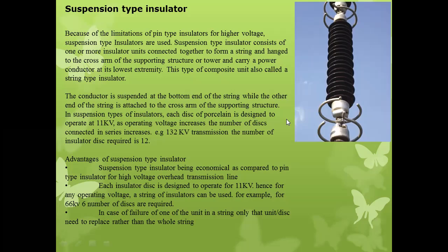In case of failure of one unit in a string, only that unit or disc needs to be replaced rather than the whole string. In the case of a pin insulator, if any unit gets ruptured or damaged, we have to replace the whole insulator. But in the case of a suspension insulator, if any one unit gets damaged or ruptured, only that unit or disc needs to be replaced rather than the whole string. That's why it is advantageous.